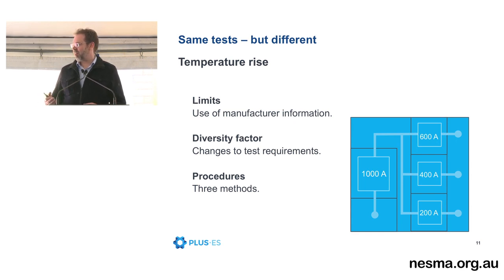It's recognising that it's not realistic that that group is going to run every single unit 100% all the time. So this is the diversity factor. However, if you have an 800 amp unit running diversity factor 0.75, you still need to prove that that 800 amp unit on its own can run 800 amps. So it actually increases the testing quite a lot.